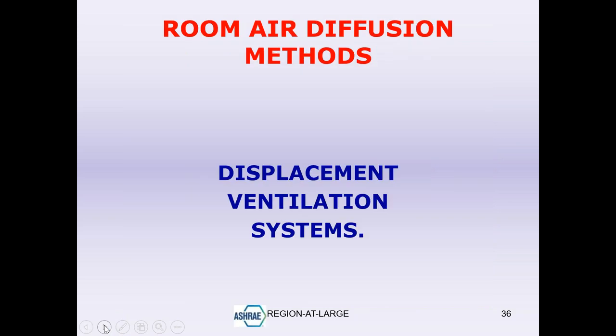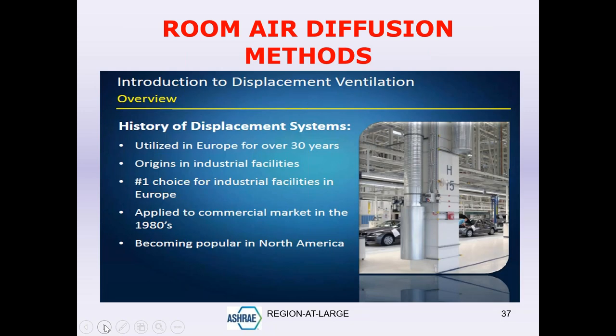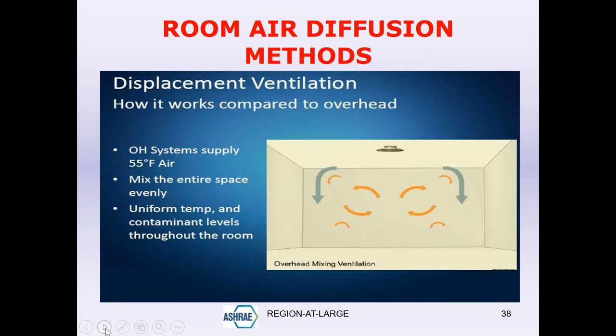That brings us to the next system: displacement ventilation. This is not new — it has been around for a long time, starting in Europe and used primarily in industrial facilities, but it's now become quite popular for occupied spaces as well. In an overhead mixing system, air is supplied from the top far from the occupied zone at around 55°F, everything mixes thoroughly, and the occupied zone is maintained with uniform temperature.